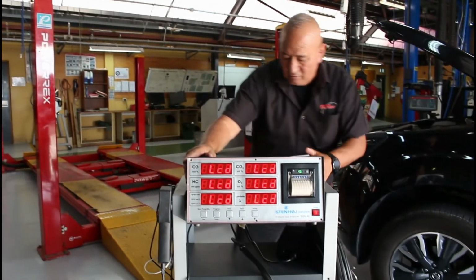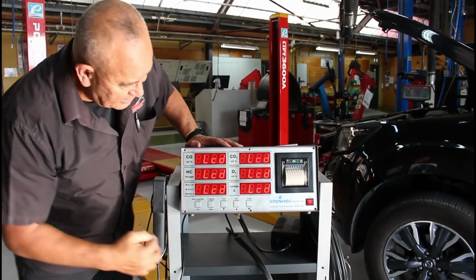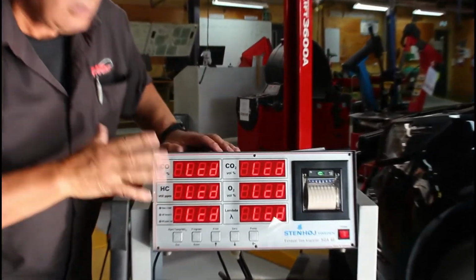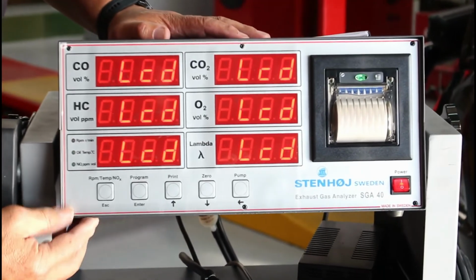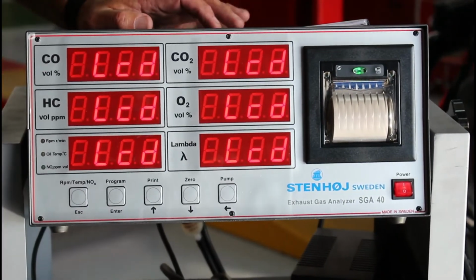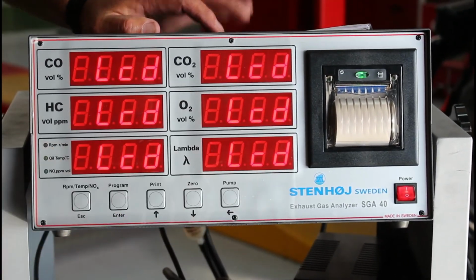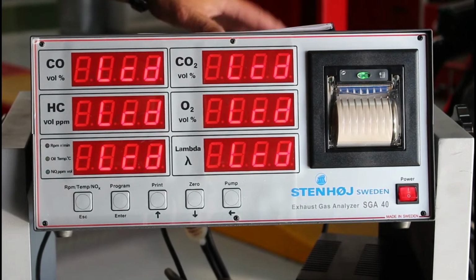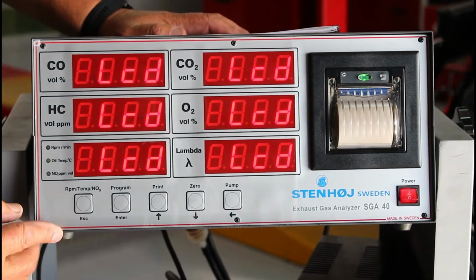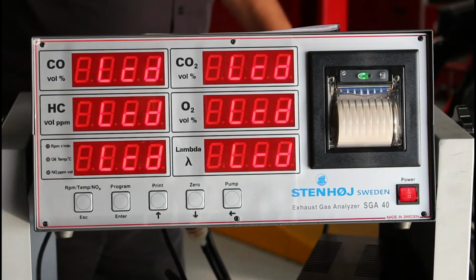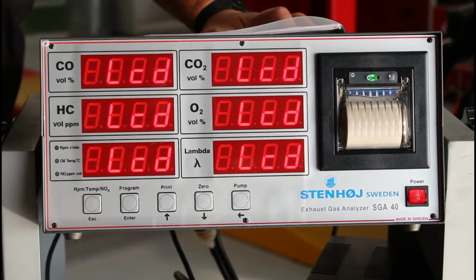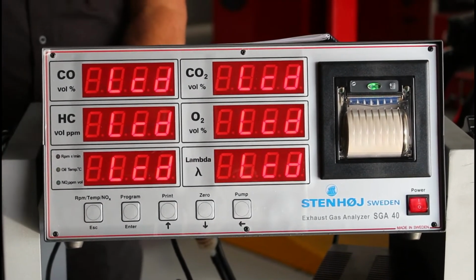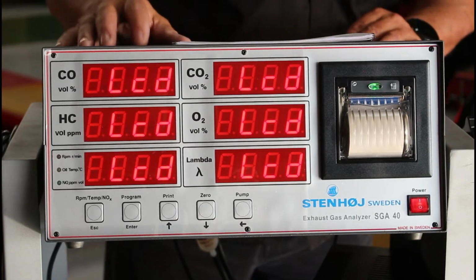On the front you'll see all your meters, HC, CO, all your standard stuff you're going to see with a full gas analyzer. Lambda and CO and percentages and so forth. If you've got NOx fitted, you'll have a special NOx sensor for the back to be able to read NOx as well.